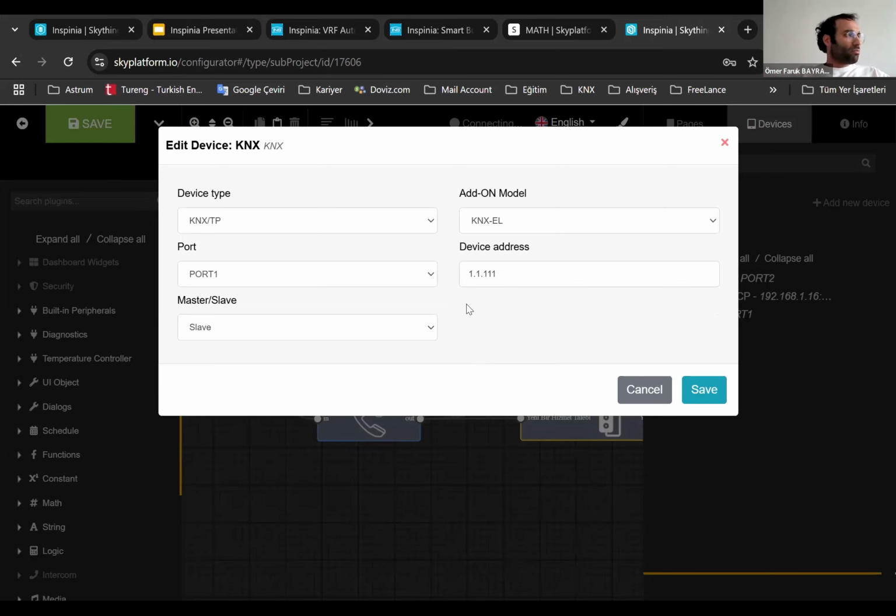So, you know, most KNX devices send the last status after turning on again after an electrical power failure. But if they don't send the last status, the panel can ask with the master option.